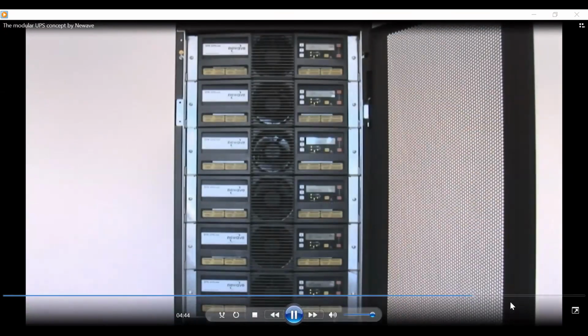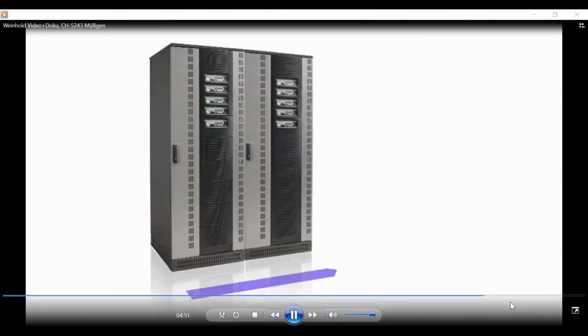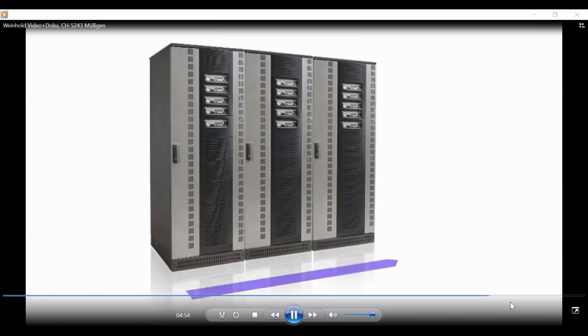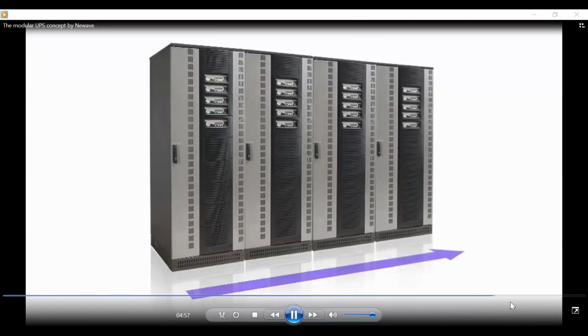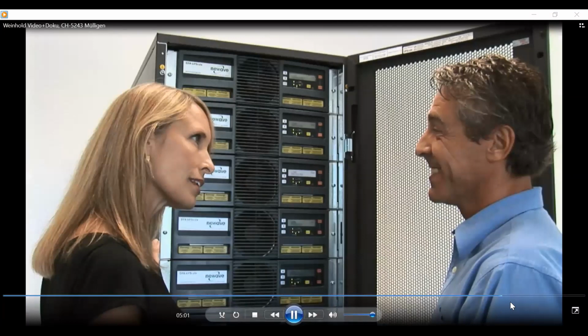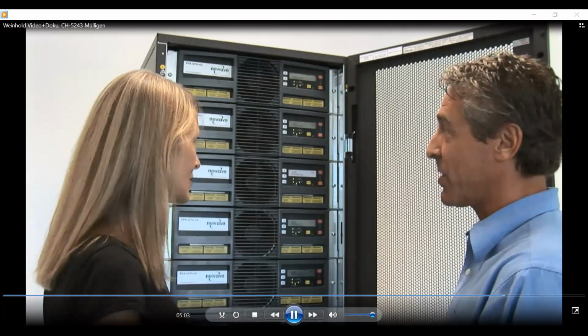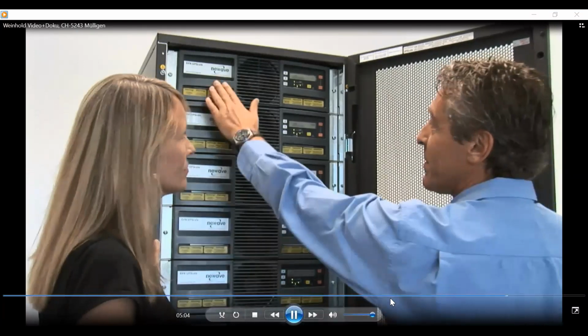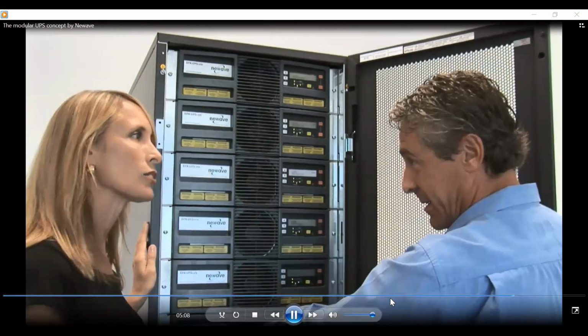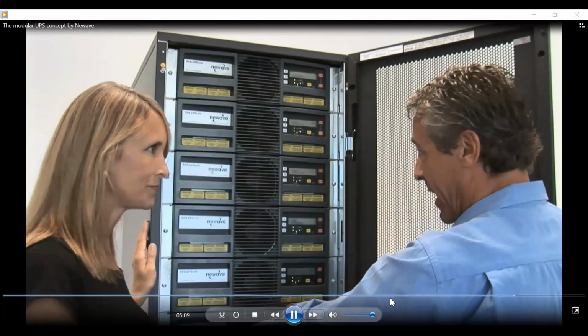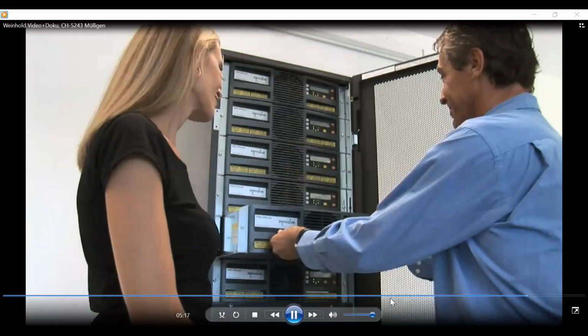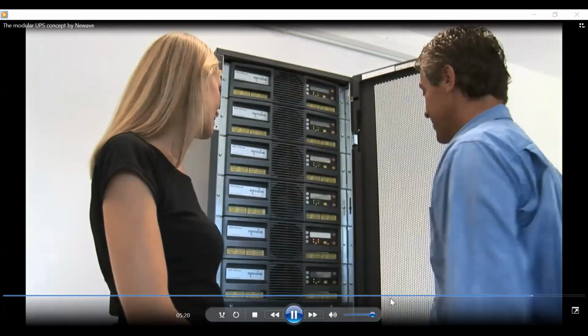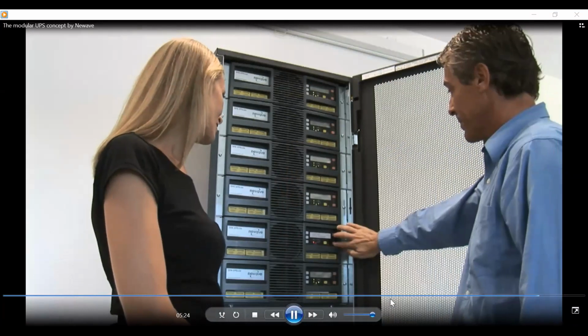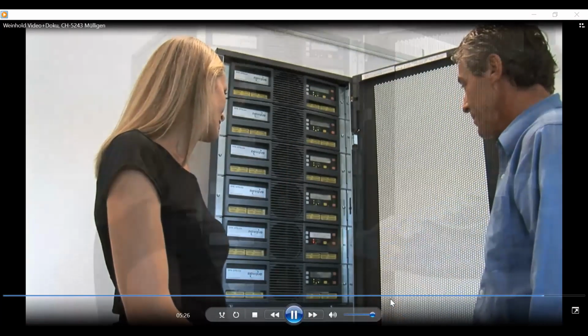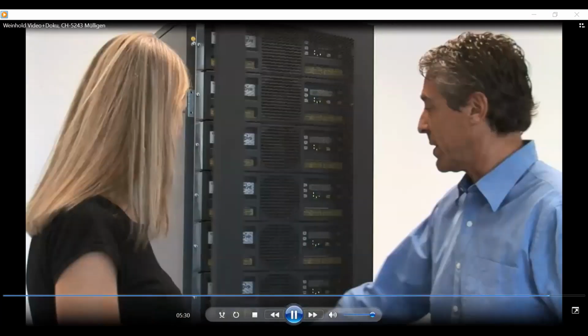Horizontal scalability is used if additional capacity or redundancy is needed. Independent UPS systems can operate in parallel configuration, achieving the required power capacity. The optimum parallel UPS solution is only achieved with systems that provide a true, hot-swappable, scalable, and modular architecture. True modular parallel UPS solutions enable organizations to simply and cost-effectively expand their UPS system's power and availability. The result is improved efficiency, lower cost of ownership, and better customer service through high availability.